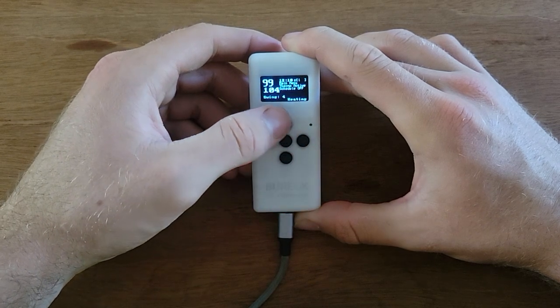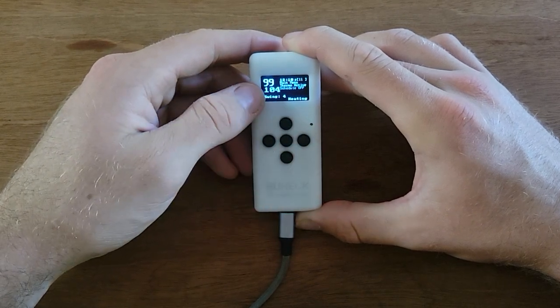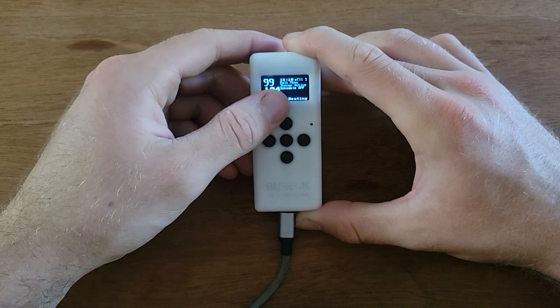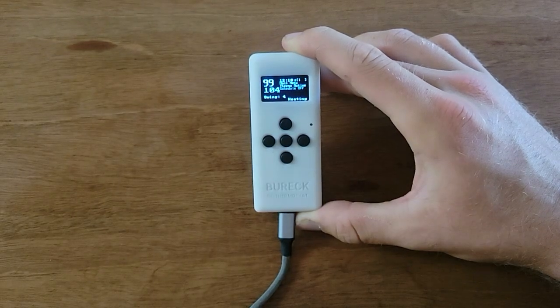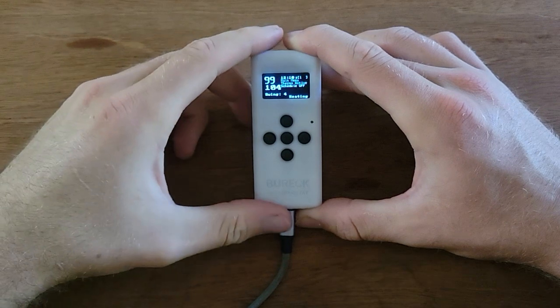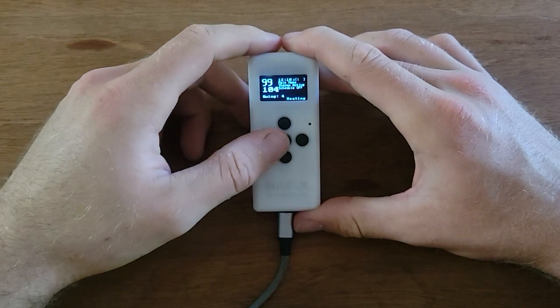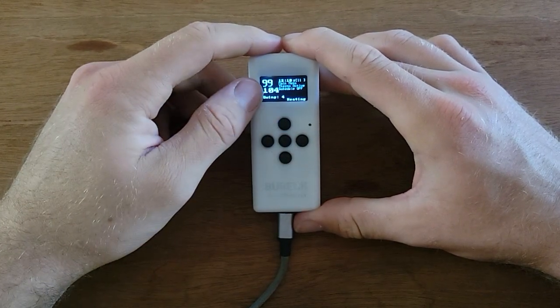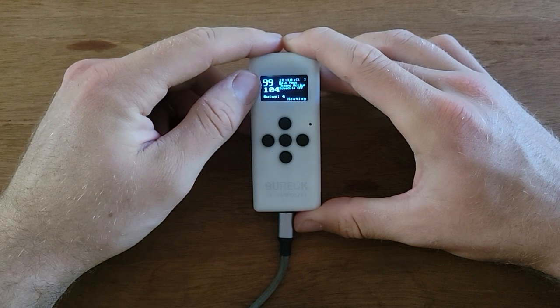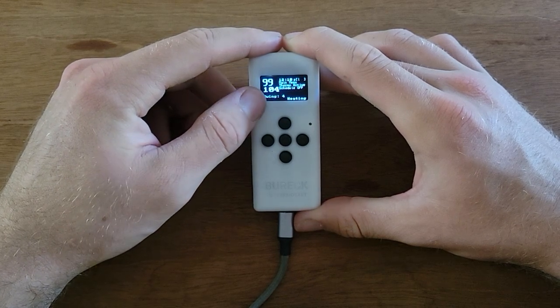There we go. Once you get up to, I think it should have actually just been on at 103, heating will appear in the bottom right corner, which indicates that the thermostat is currently telling your heater to heat. And it did not do that when we got just above 99 or when we got to 99. That's because the swing is 4.